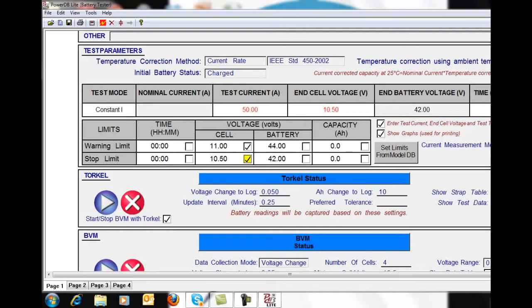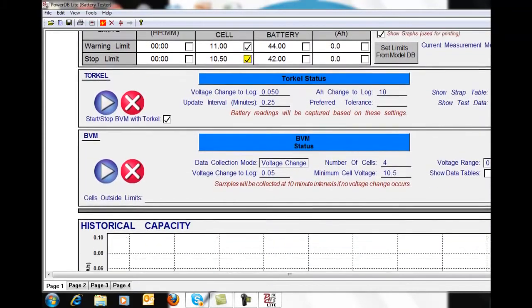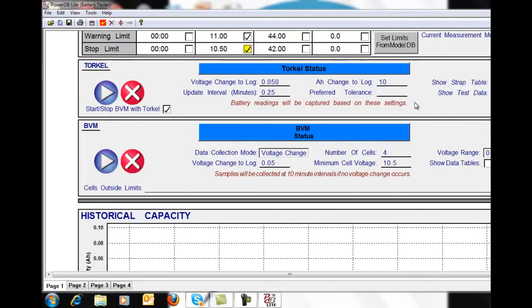Now, as we move down the worksheet, we see the controls for the Torkel and the BVM. For the BVM, I'm testing, instead of a 2-volt jar, I'm actually treating each jar, which is technically 12 volts, as an individual cell. So I'm going to tell the BVM that I'm on the 0 to 20 volt range. On both, I want to go ahead and show my test data on my form. And by checking the box over here, I can start and stop the Torkel through one set of controls.